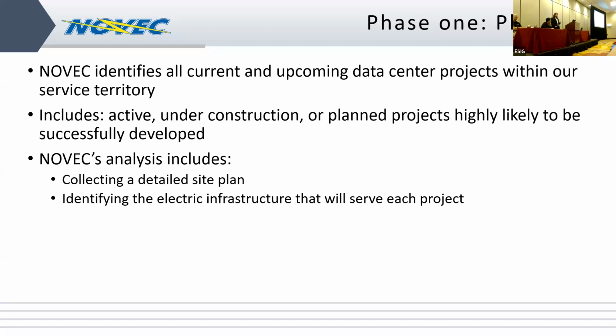The customer needs to have identified some land, they need to own that land, it needs to be zoned for data center. We need a site plan. We need to know where the substation is going, where the transformers and breakers will be, how the transmission is going to get there, how the distribution is going to be laid out. So by the time it gets to the load forecast, we know the project in and out, forward and backwards.